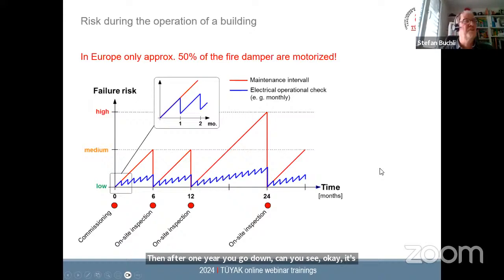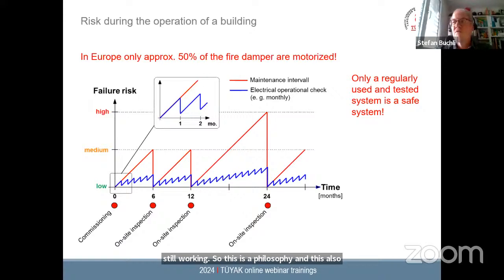So this is a philosophy, and this also lets me give the advice which I say not only to fire dampers or to any safety system actually. Whatever system you have, safety system, you use it on a regular basis, because then you know it's working or it's not working. And usually I often compare fire dampers also with fire doors.